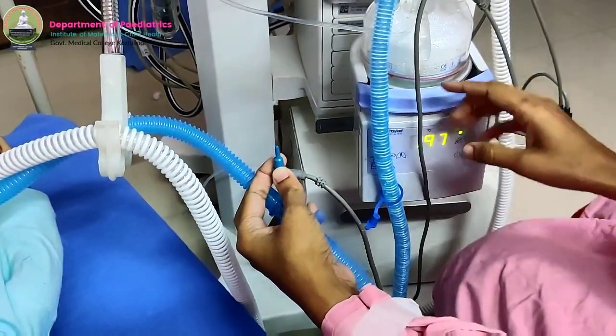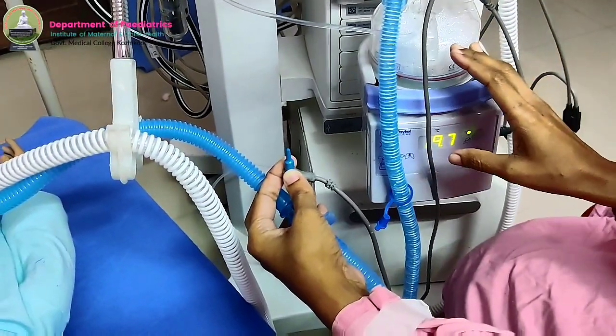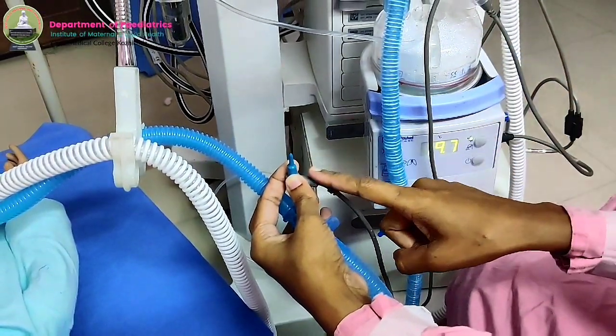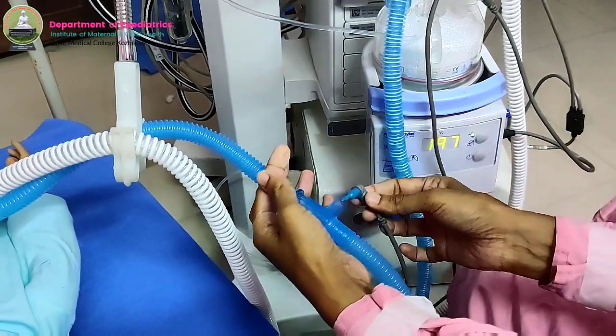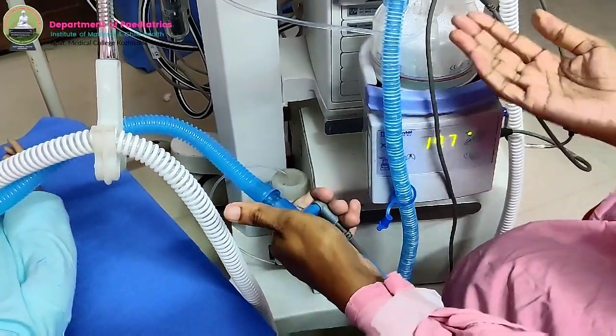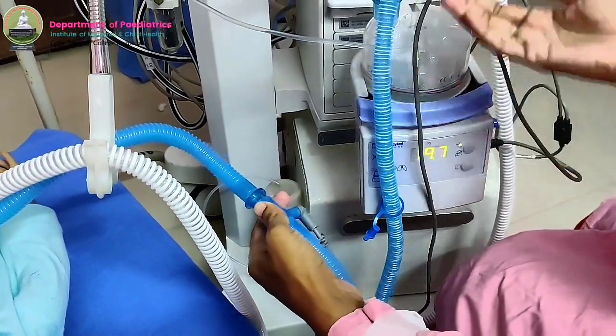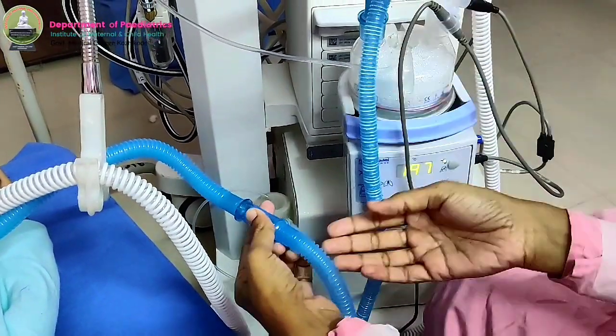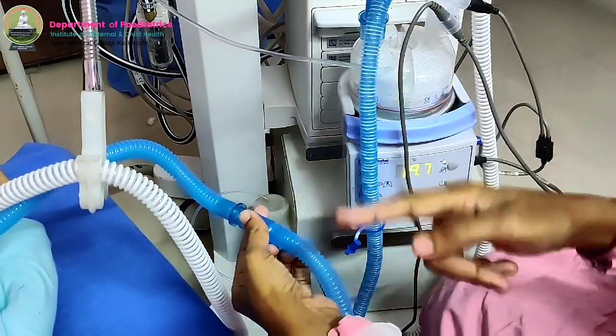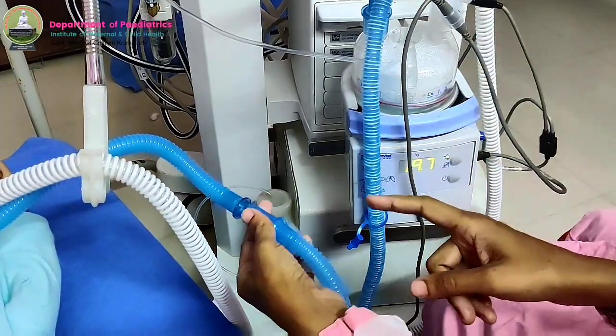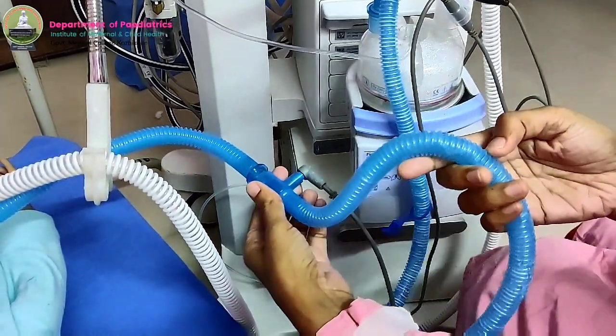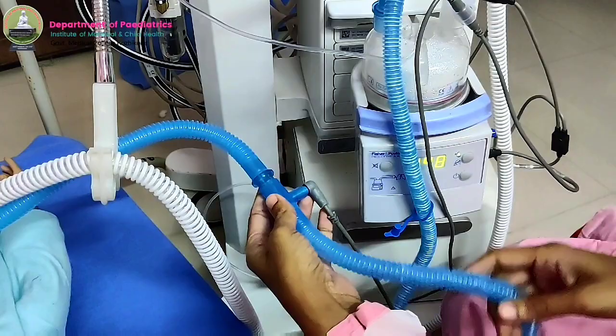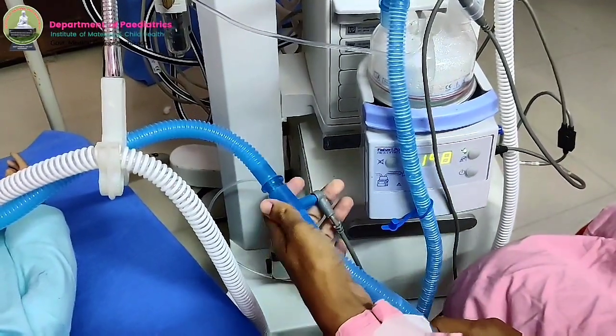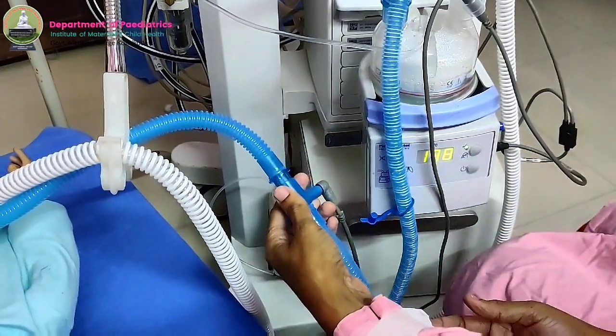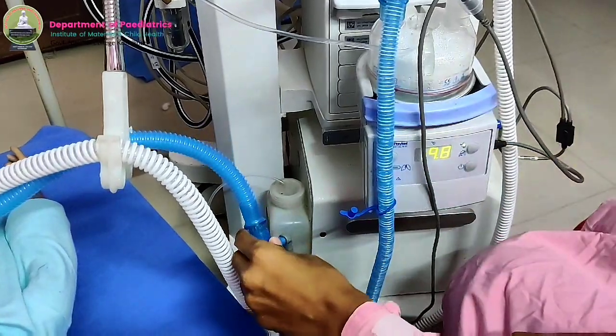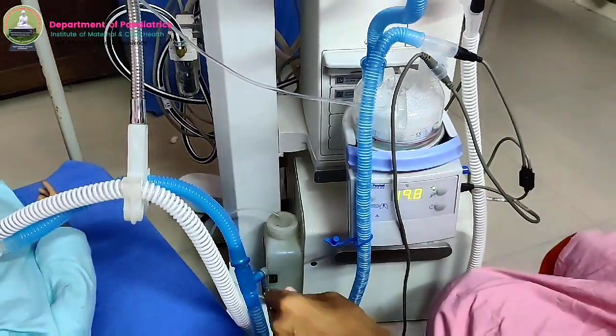The humidifier is a servo control machine, so it will sense that the temperature is low and in response it will heat up the water here. More and more vapor will be produced and more water condensation occur. This occurs in a vicious cycle and the patient circuit will be loaded with water. It can obstruct ventilation. It may cause auto triggering by the ventilator. So this is also an important point.